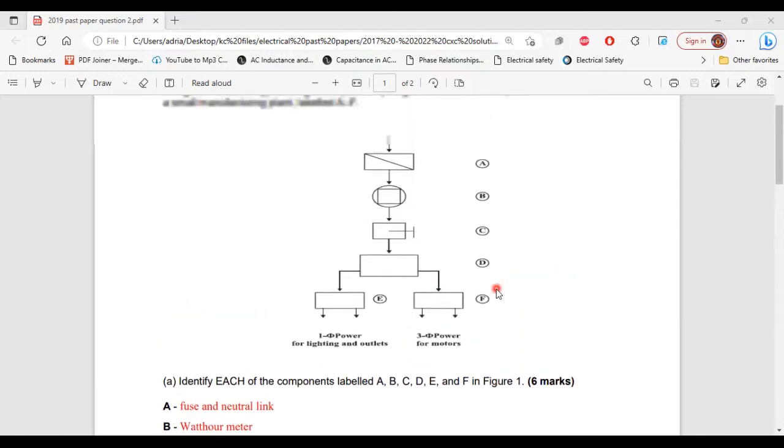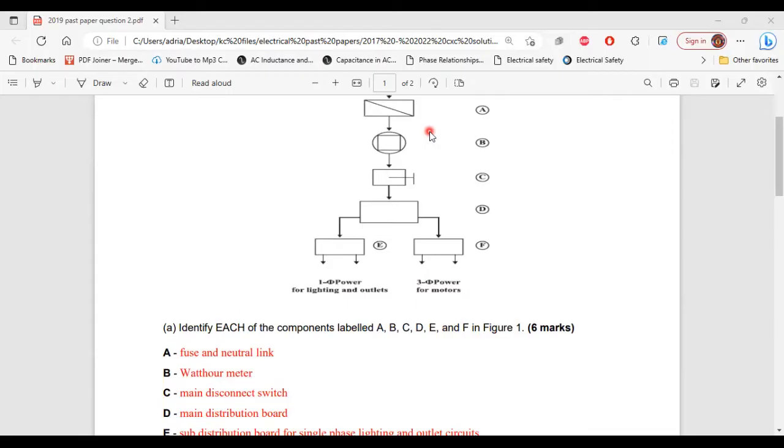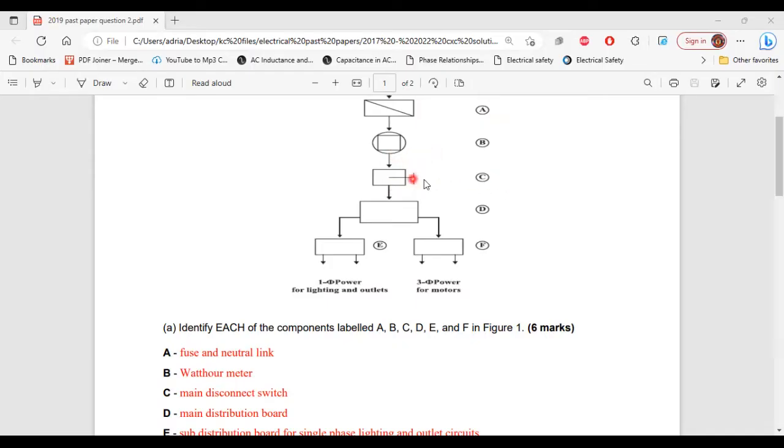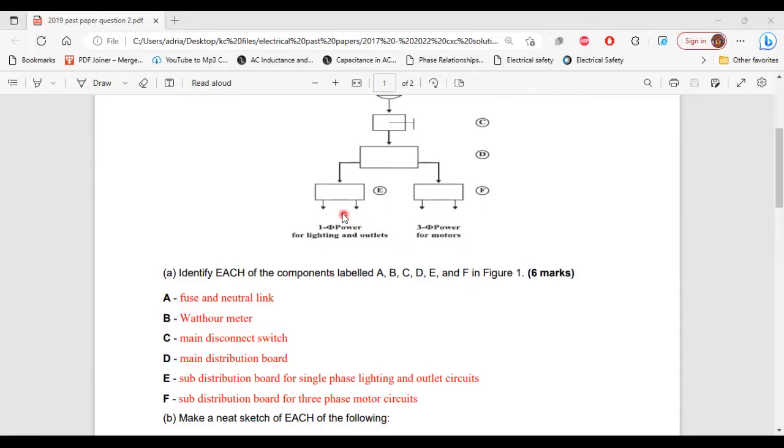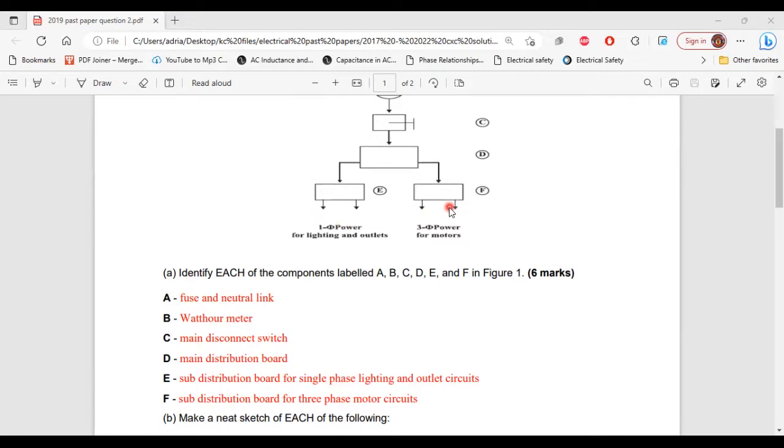All right, so A is the fuse and neutral link, B is the watt hour meter, C is the main disconnect switch, and D is the main distribution board. E is a sub-distribution board for single phase lighting and outlet circuits. F is a sub-distribution board for three-phase motor circuits.